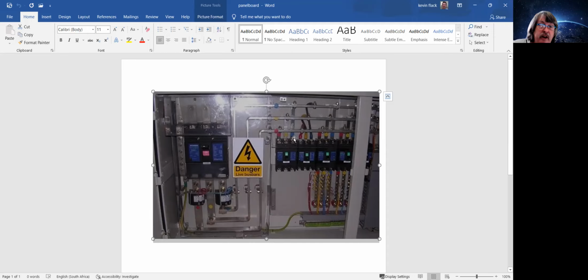That's another thing. If we look here, these busbars are basically extreme. Well, the side one is extremely close to the breaker. It's probably within the area where the manufacturer says, I want 15 millimeters or 20 millimeters till any metal part. And if you look at this busbar running through here, it's probably in contravention. I don't know what it is offhand, but it's not great to be so close. The busbars look further apart from each other than they do to the breaker, but the breaker is going to have a gas out here. So if you are a manufacturer, please look out for that type of thing.